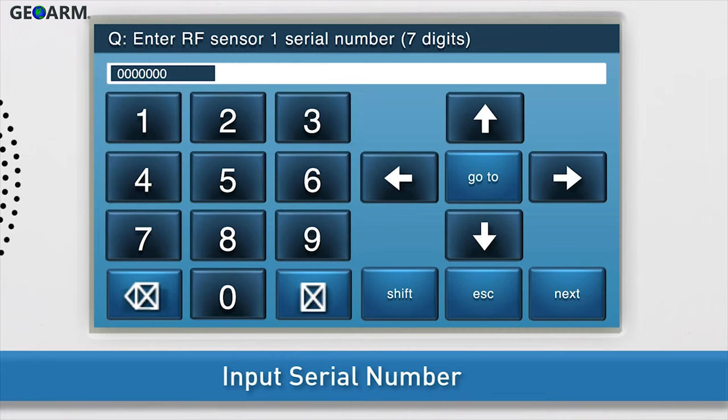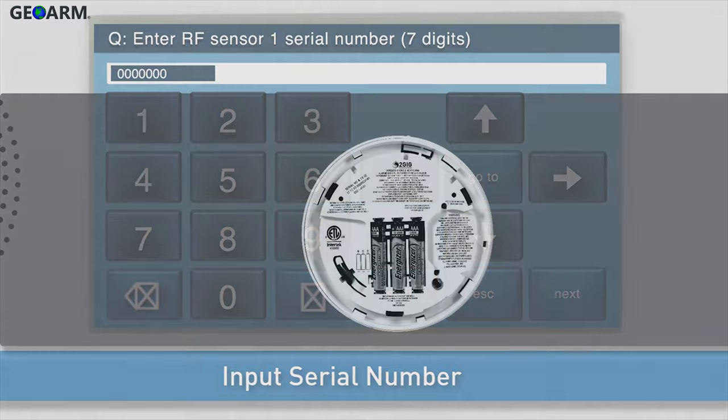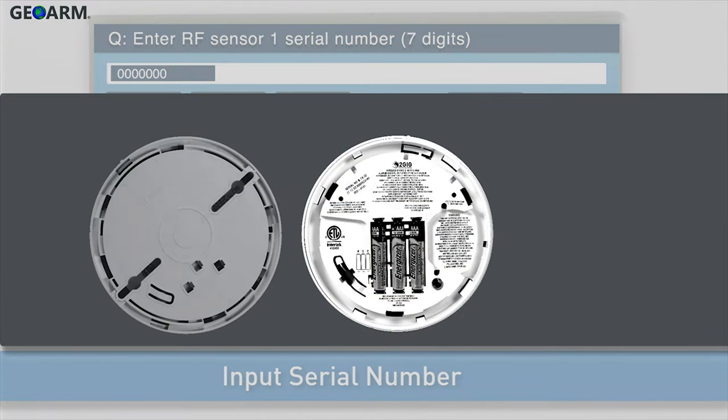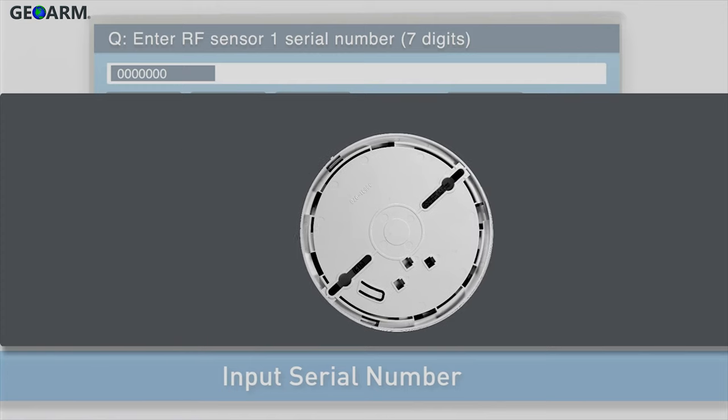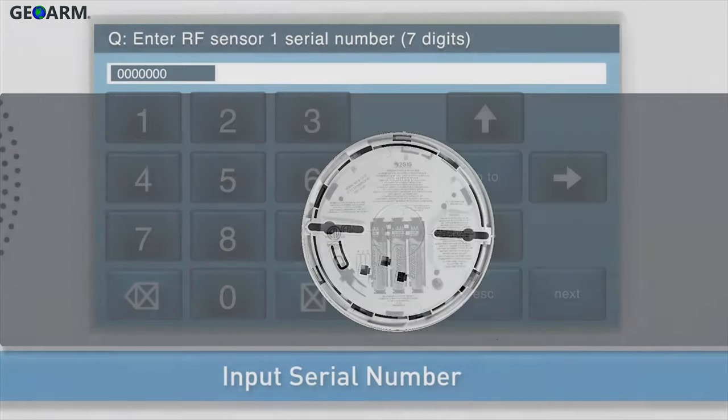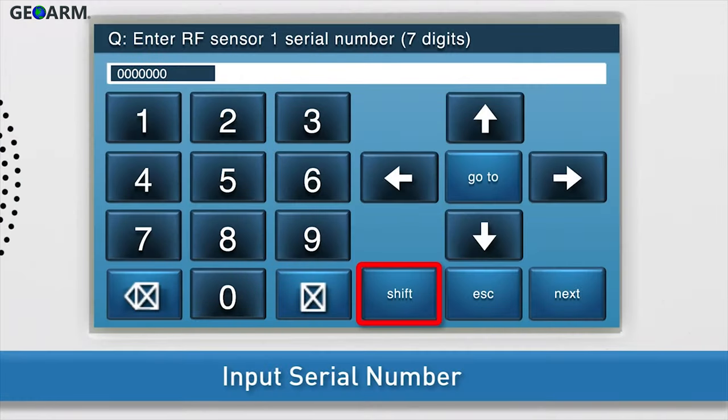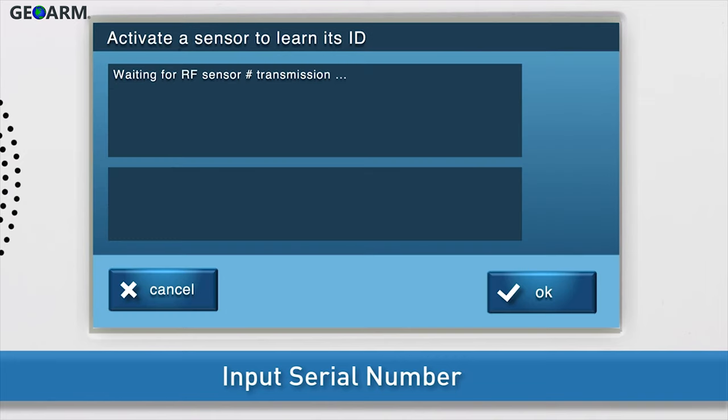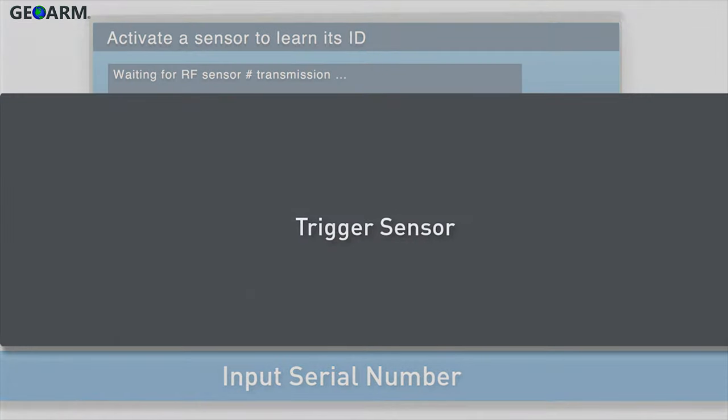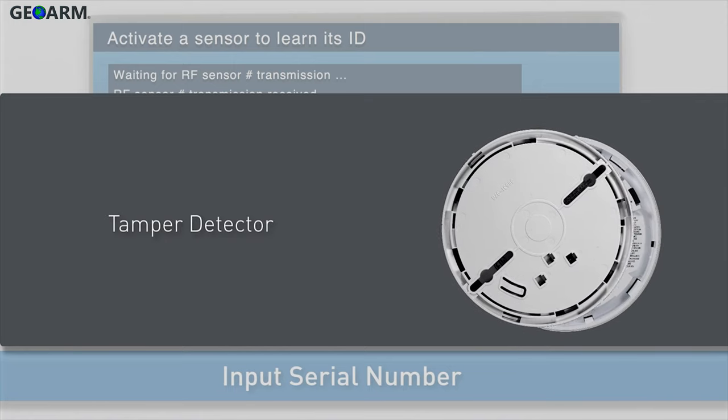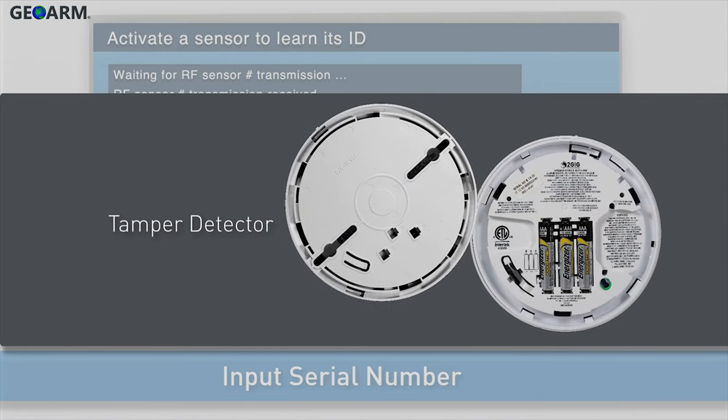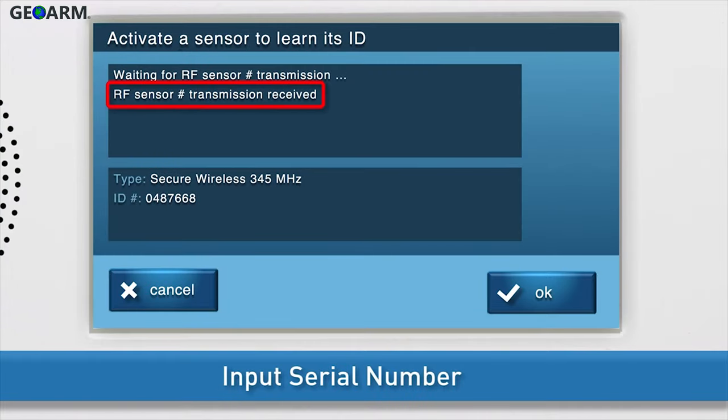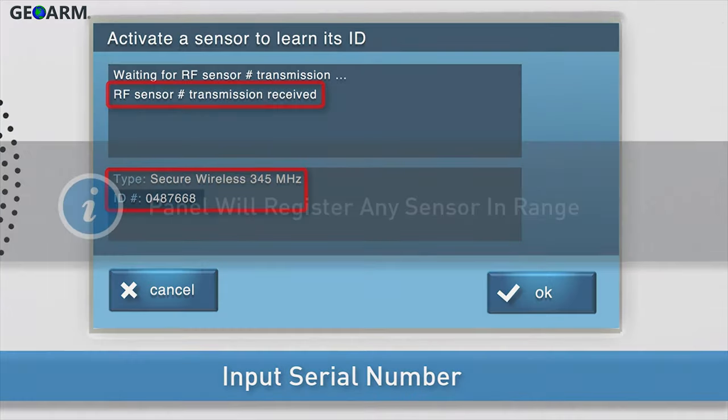You can either add the serial number with the panel's on-screen keyboard or add it in wirelessly. If you choose to add the serial number wirelessly, first insert the batteries, if you have not done so already, and then attach the mounting base and turn the detector clockwise to secure. Press SHIFT, then LEARN. You will see a message that the panel is waiting for the sensor transmission. Trigger the sensor. Twist the detector counterclockwise to remove the mounting base.